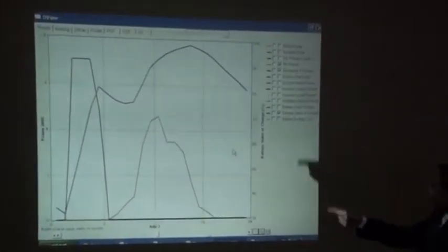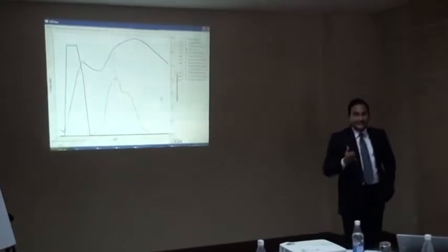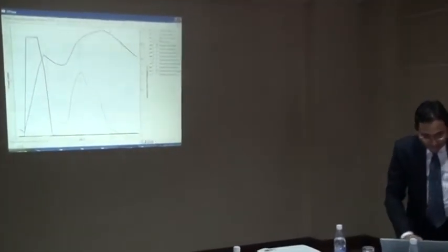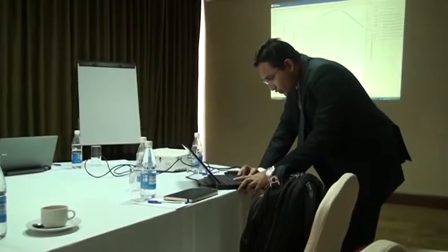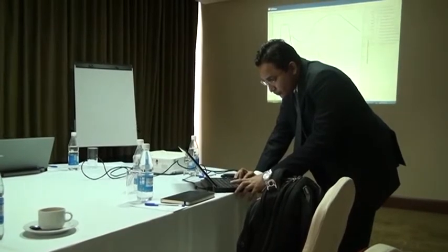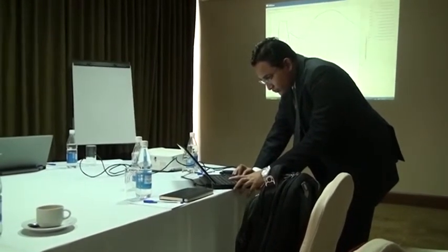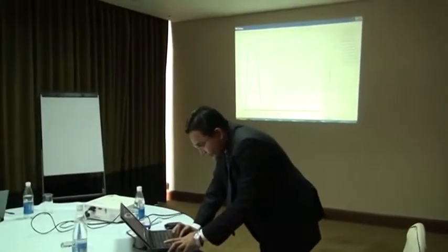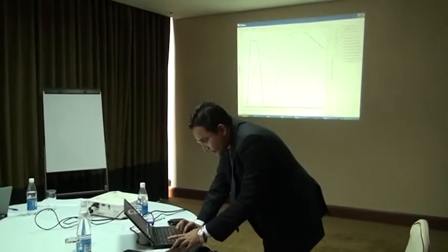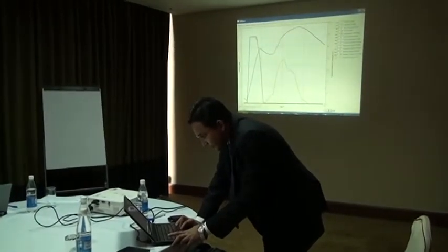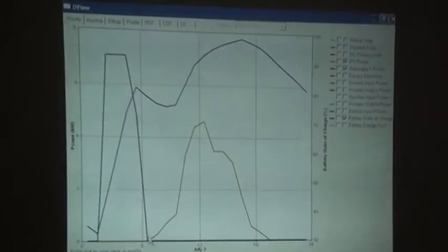And what is happening, the black line which is going up and flat and then completely gone down, this is actually a genset situation. So the diesel genset is kicking off, it's about 2 in the morning. What's the time on this? 2 a.m. Yes, the genset is kicking off in the morning, and it's running on a very high load, about 6 kilowatt, and then continuing for a few hours, and then it's going down again at about 7 a.m.